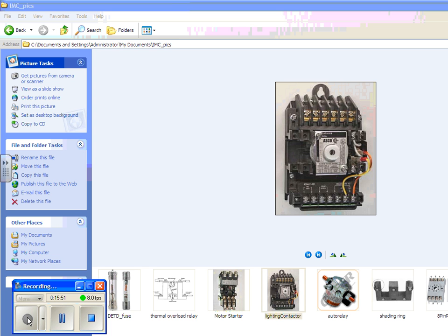Lighting contactors are very often mechanically held. Once they're pulled in by the on relay, they have to be released. You have to have a latch that's released and lets them spring load open, or a physical push-them-open relay, or plunger I should say. So fairly often, lighting contactors are mechanically operated. They're a relay to turn them on, a relay to turn them off, and they serve a very special purpose: turning something on, leaving it on for a long time, turning it off. Okay?